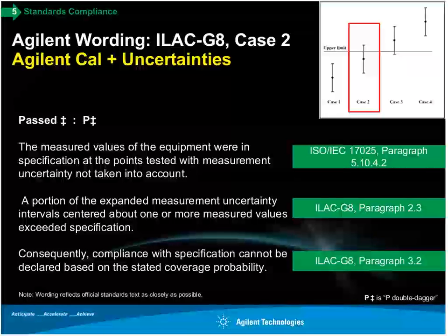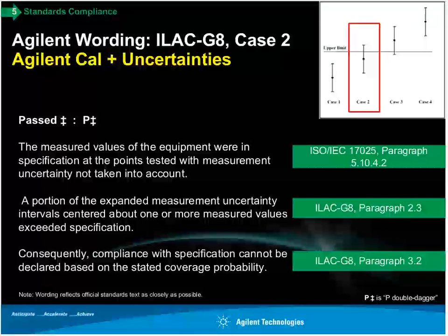Of course, there is a situation, and it's quite common, where the uncertainty of measurement is dominated by the performance of the instrument itself. Now, in that case, it doesn't matter if you go to a better laboratory with a lower uncertainty, it's not going to significantly affect the situation. So you wouldn't therefore have the lowest uncertainty work done on a relatively mundane instrument. And people do make that mistake. I think it's important for users to understand that if they have a rudimentary instrument, they're only going to get rudimentary performance out of it, however low the uncertainty of the laboratory that they've chosen.